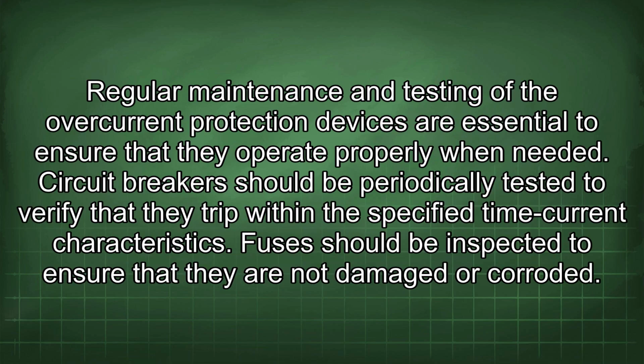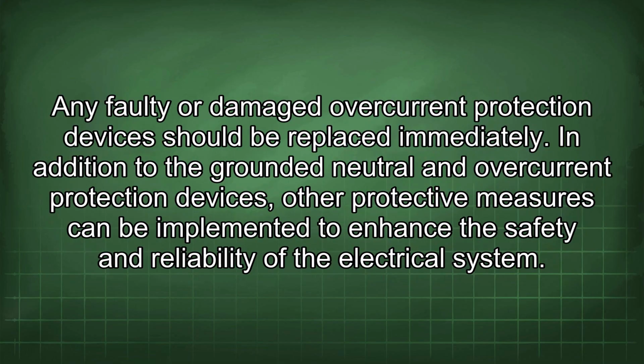Regular maintenance and testing of the overcurrent protection devices are essential to ensure that they operate properly when needed. Circuit breakers should be periodically tested to verify that they trip within the specified time current characteristics. Fuses should be inspected to ensure that they are not damaged or corroded. Any faulty or damaged overcurrent protection devices should be replaced immediately.